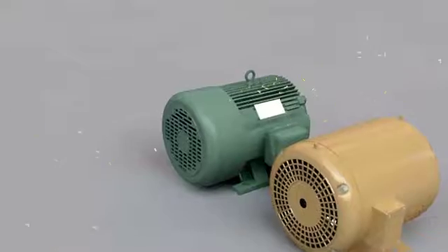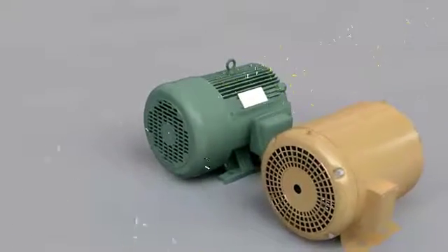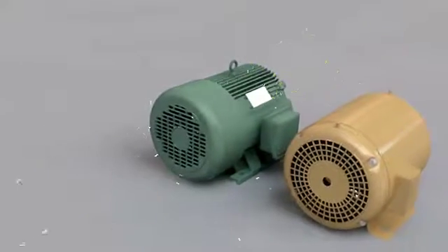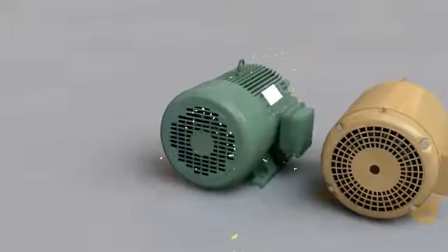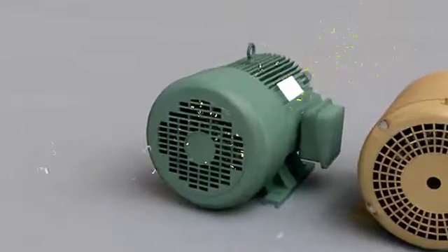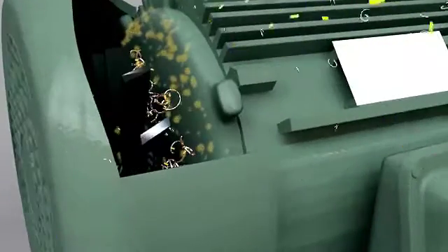A totally enclosed fan-cooled motor is different. The windings are sealed from the environment. Here you can see from the demonstration, the air, sawdust and metal chips get pulled in from the cooling fan but do not enter inside the motor. Instead, they will pass over cast iron fins for cooling, while the windings stay free from foreign materials.